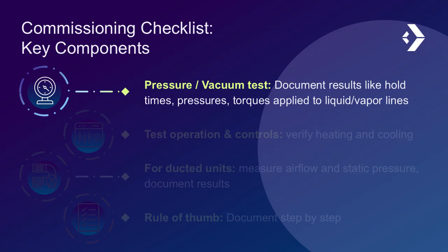Now, we're on to the actual commissioning tests. Document the pressure and vacuum test results used to confirm the refrigerant line is ready to be charged and can hold pressure when it is. Record the pressures used and measured, and the hold time for both. Then document if you used the factory charged refrigerant reserve and if you added more.